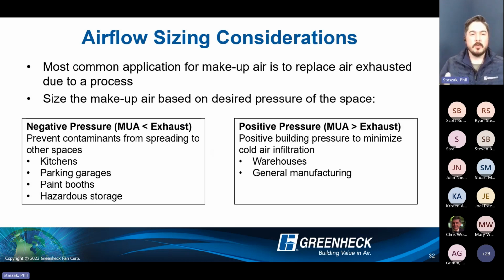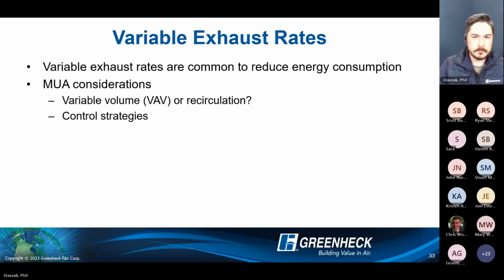That's where you typically want to size for larger exhaust and a slight negative pressure as it comes to your building. Now, positive pressure applications, where you want your makeup air to exceed whatever is being exhausted, generally for cold air infiltration, are warehouses and general manufacturing, more of the space heating functionality, trying to push infiltration out.